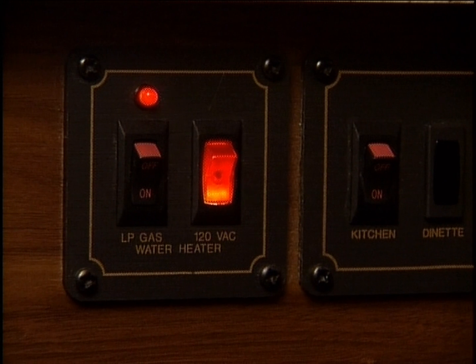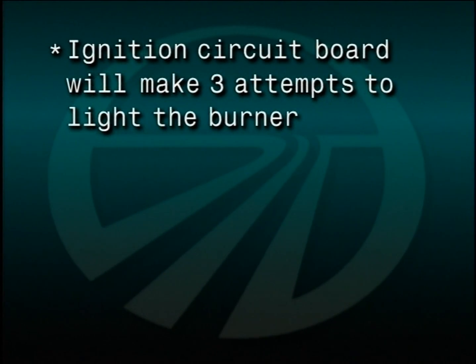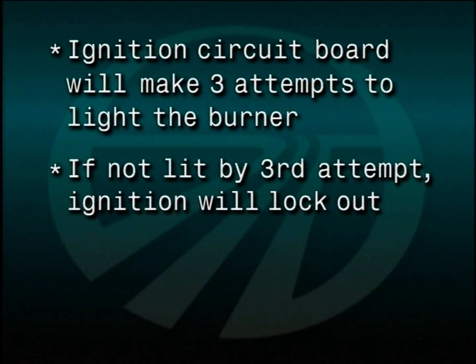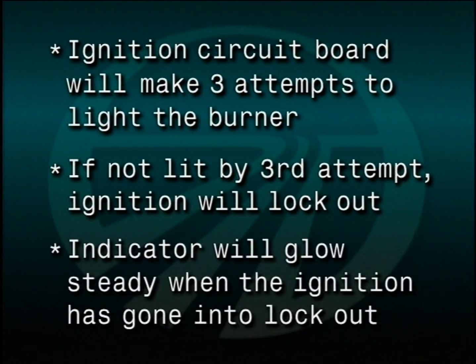This is the gas burner. You will hear an audible roar from the burner when ignited. The indicator light will illuminate briefly, then go out when the water heater is lit. The automatic ignition circuit board will make 3 attempts to light the burner. If the burner does not light by the 3rd attempt, the ignition circuit board will go into lockout. The indicator light will glow steadily when the ignition cycle has gone into lockout.